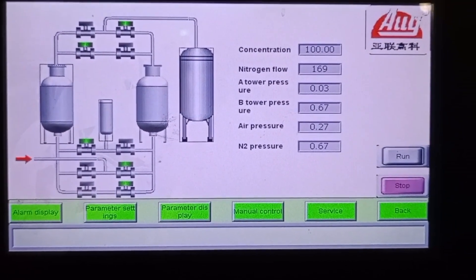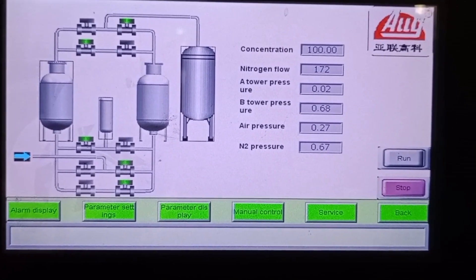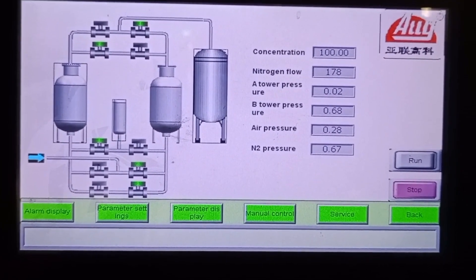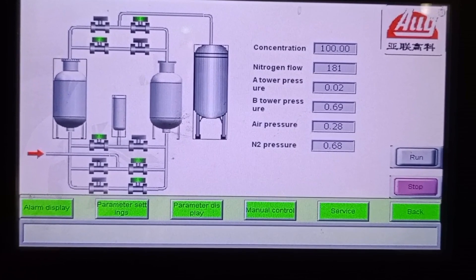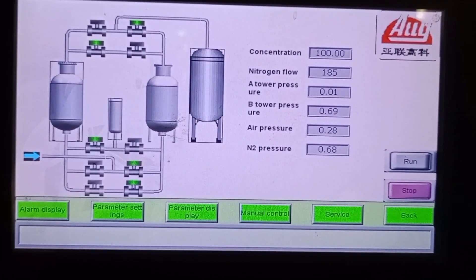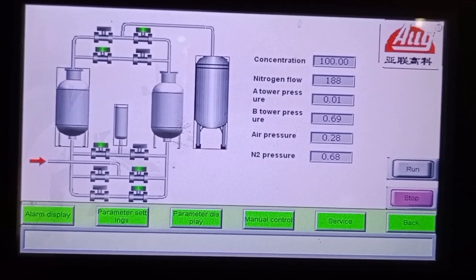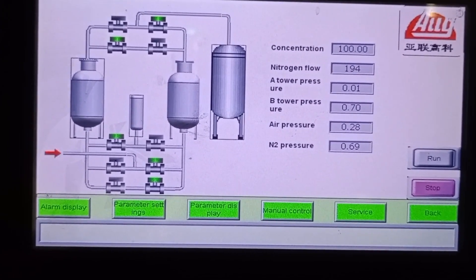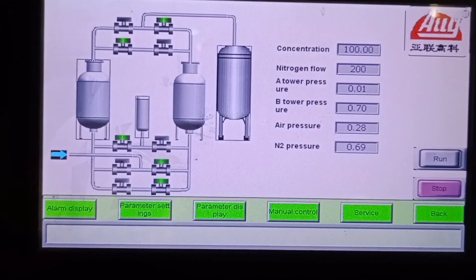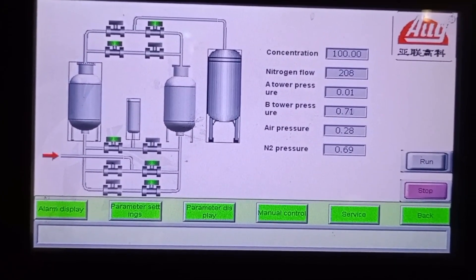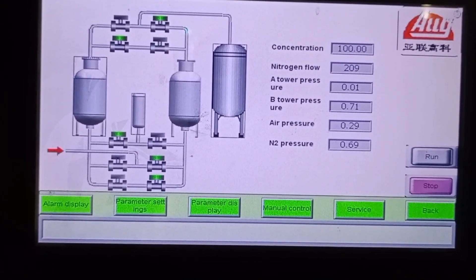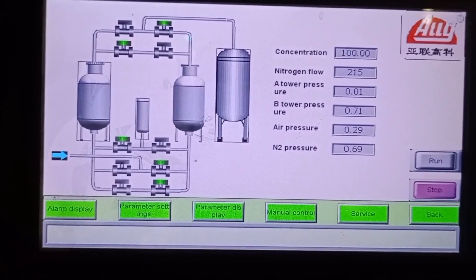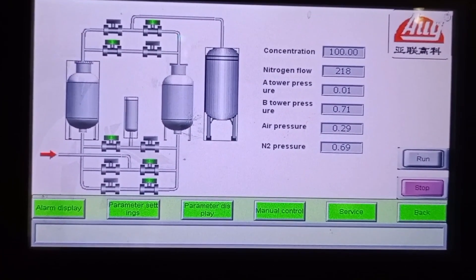From the HMI unit, we can observe when the valve will open or close. By the solenoid valve, the on-off valves will open and close. From the pressure gauge, we can see the pressure at the pressure swing adsorption unit. Depending on the time sequence, the PSA unit changes and the process remains continuous. When any problem occurs, considering this process sequence, you can easily maintain the system and run the process smoothly.